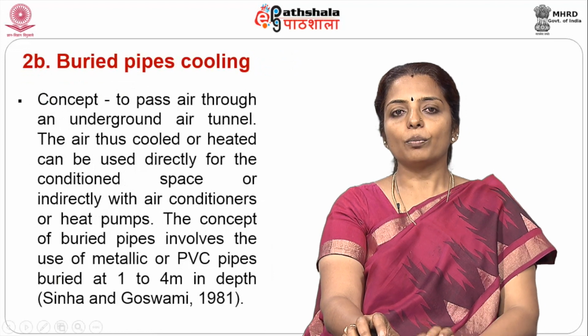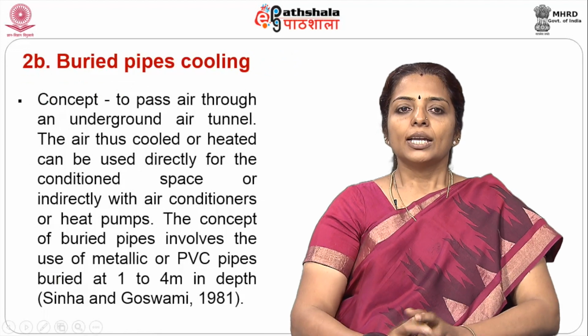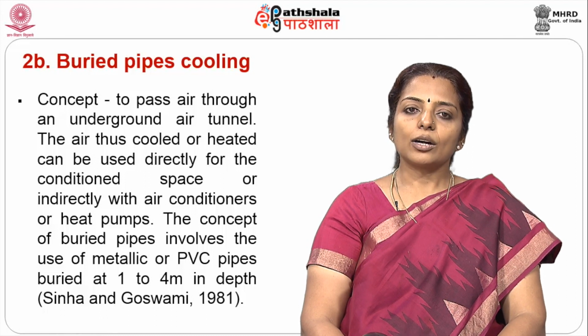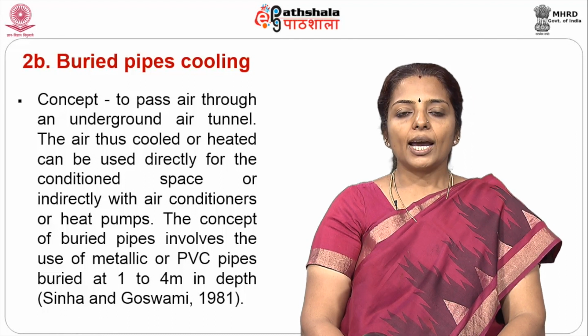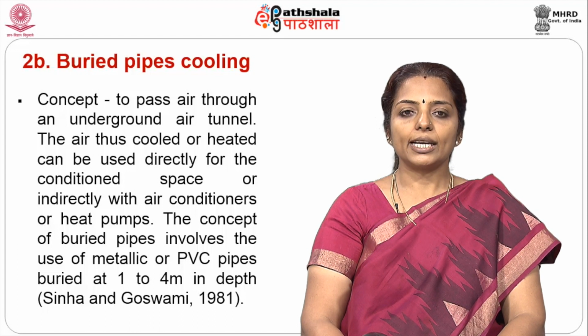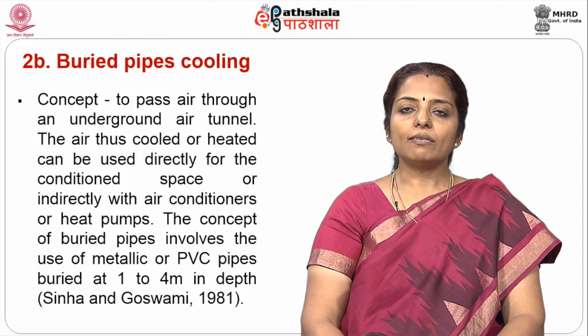Next, we move on to buried pipes cooling. In this concept is to pass air through an underground air tunnel. The air thus cooled or heated can be used directly for the conditioned space or indirectly with air conditioners or heat pumps. The concept of buried pipes involves the use of metallic or PVC pipes buried at 1 to 4 meters in depth.